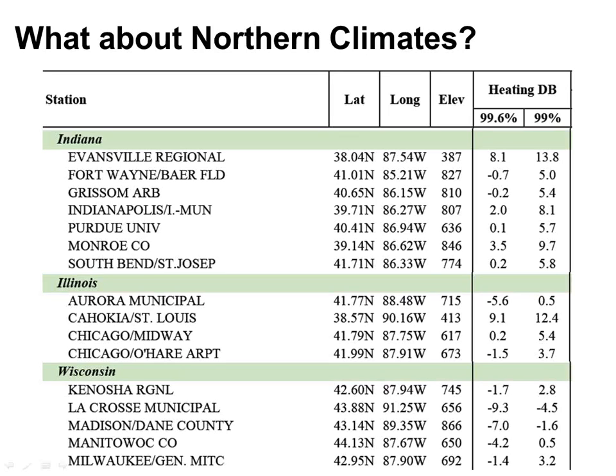So if you look at that table out of the book, and hopefully you guys all have these books at your office. If not, they're phenomenal. You should get them. Plus they're ASHRAE, and this is an ASHRAE webinar, so we got to promote ASHRAE stuff. You get 2 columns. You get the 99% column and the 99.6% column. Basically, the way to kind of think about that is 99% of the heating time of the year, the outdoor temperature is going to be above the temperature listed in this column.